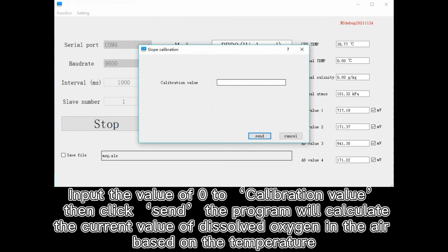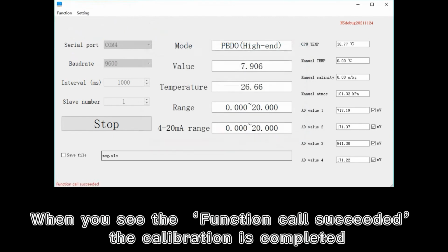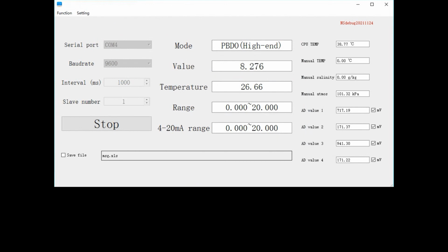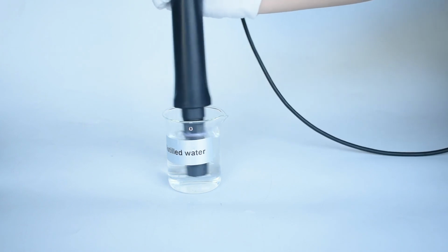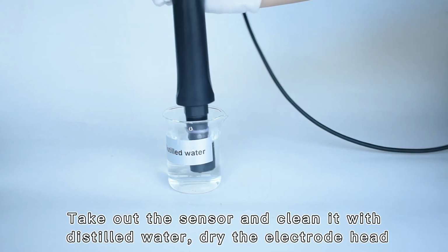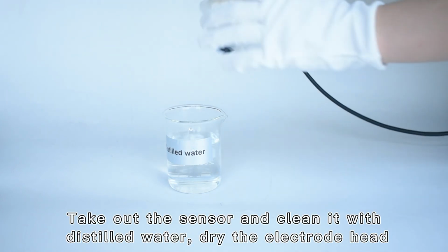Select Function, Calibration Function, Slope Calibration. Input the value of 0 to calibration value, then click Send. The program will calculate the current value of dissolved oxygen in the air based on the temperature. When you see function call succeeded, the calibration is completed. Take out the sensor and clean it with distilled water. Dry the electrode head.